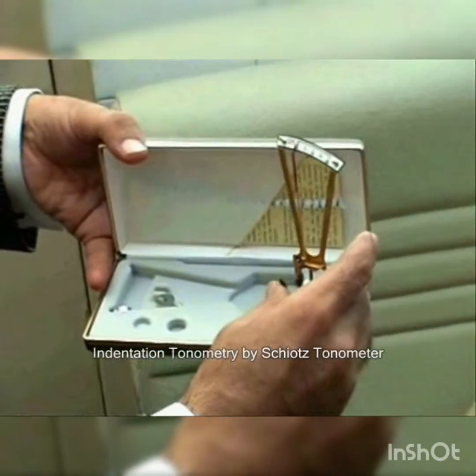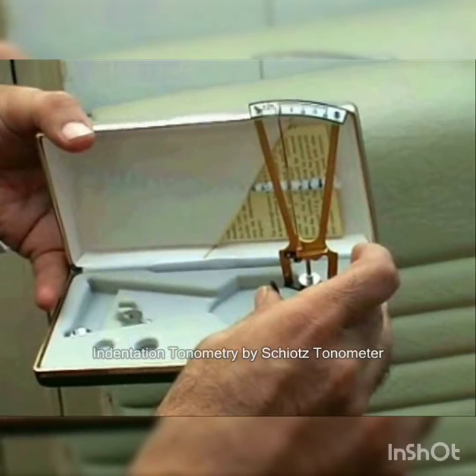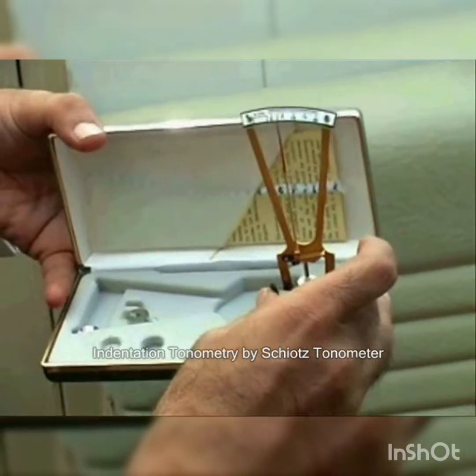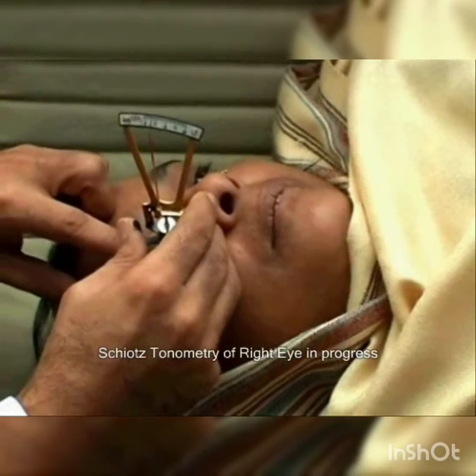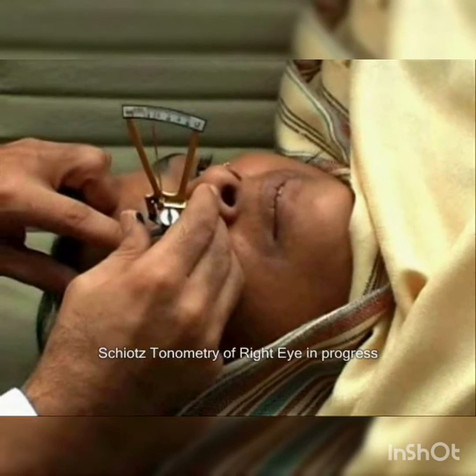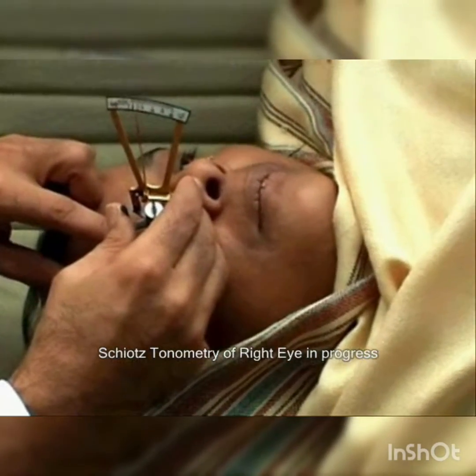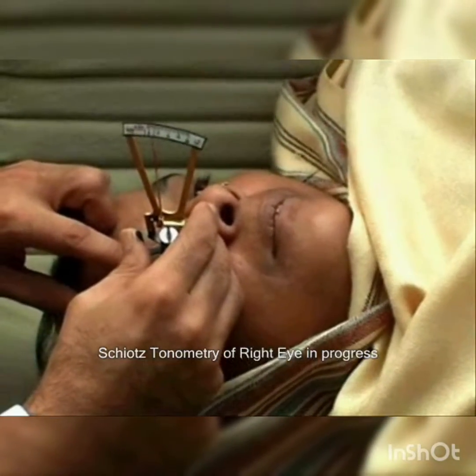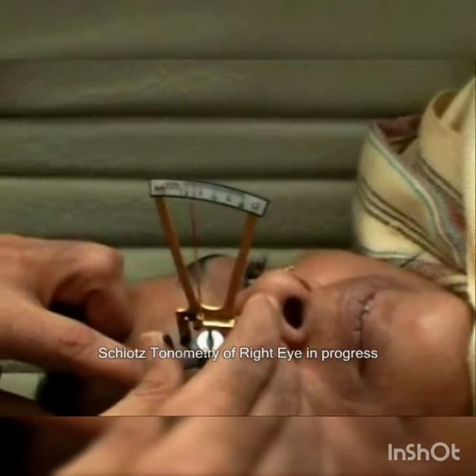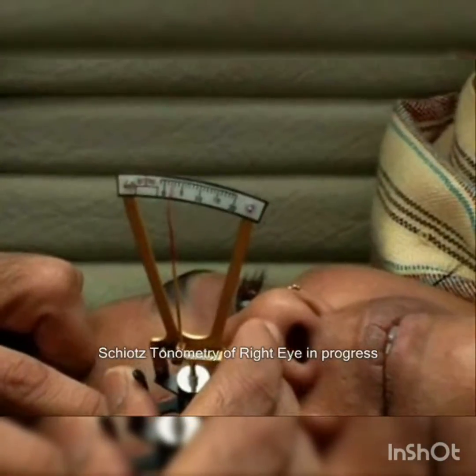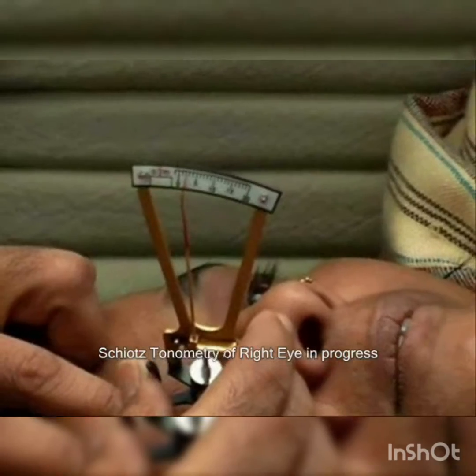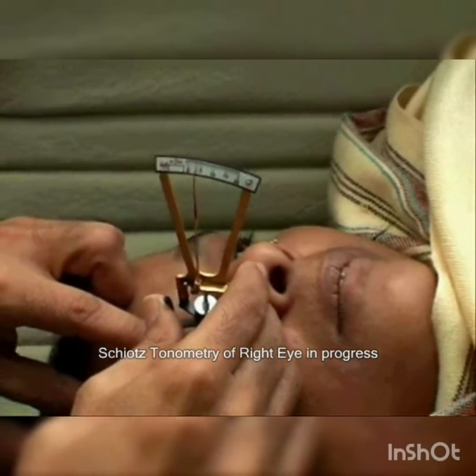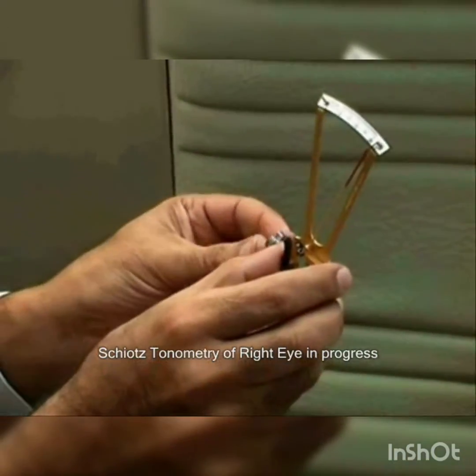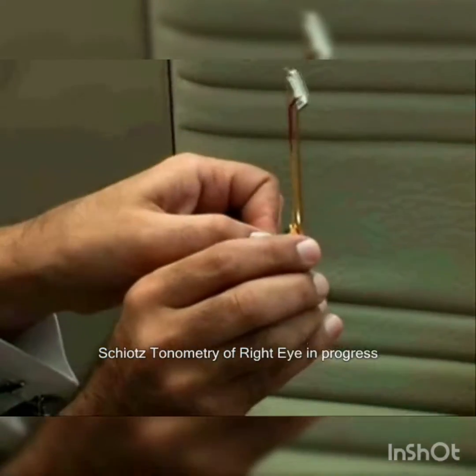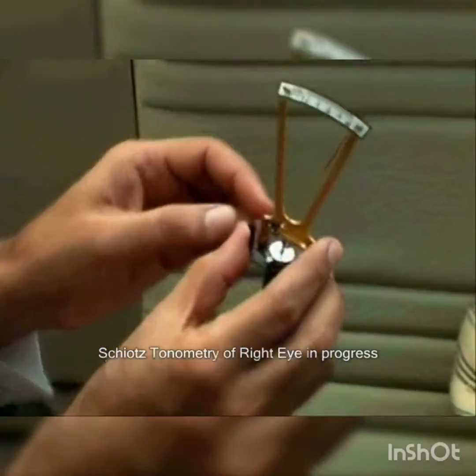The Schiotz tonometer is an indentation tonometer that measures the amount of corneal deformation produced by a given force. The indentation measures the ease with which the globe is indented by the plunger of the instrument. The soft eye is easily indented, indicating a low pressure, whereas a hard eye is indented with greater difficulty.